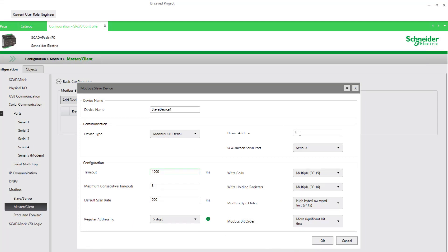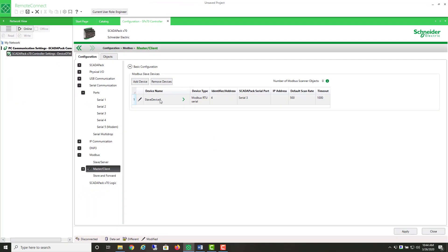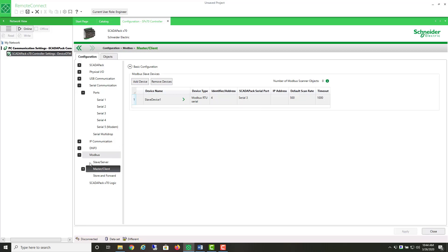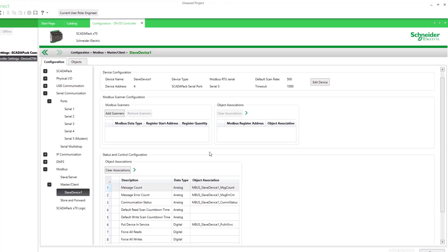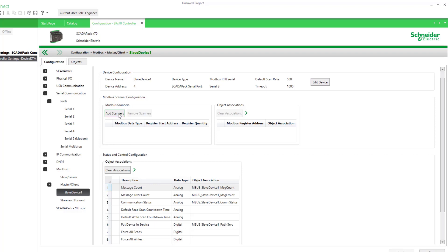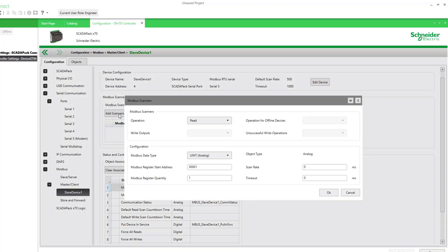I've selected my station address of four, and that's all I've selected here. Here's my slave device now. I'll apply the change, and I can either click here to begin adding scanners to it, or I can note that it's now listed under the master folder tree. Here's my new slave device. On this window, we have a summary of our slave device, the station address, what serial port it's on, and it's being scanned at a half-second per scan. The bottom area here is a list of diagnostic and control objects that apply to the device. In the center, this is where we add a range of registers to pull. So select Add Scanners.